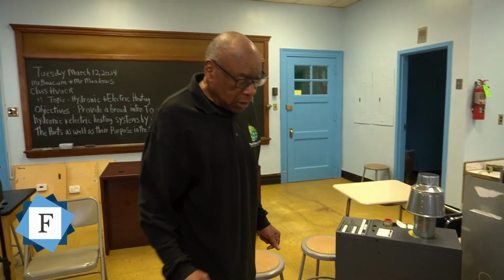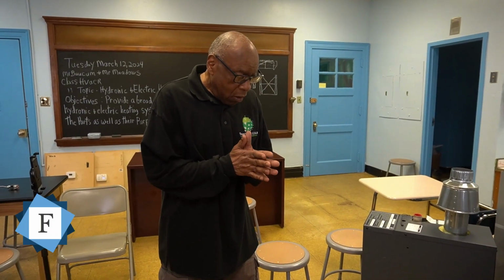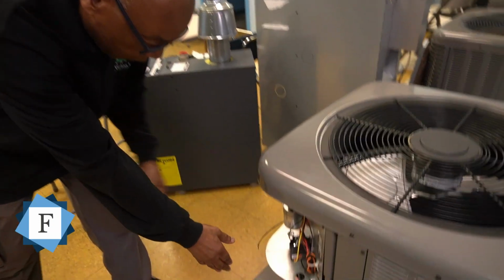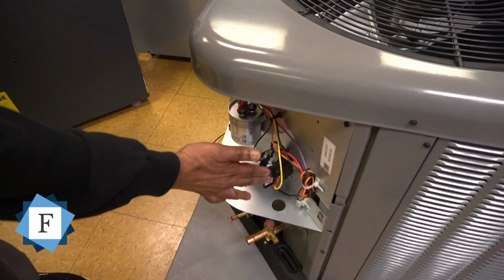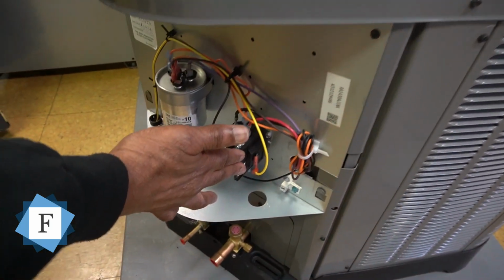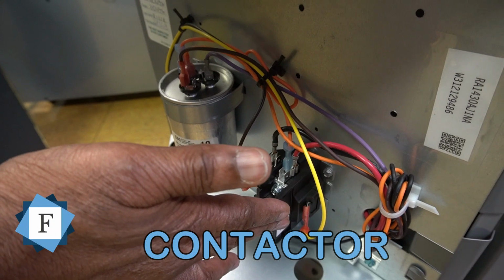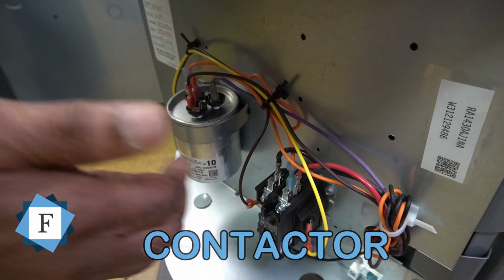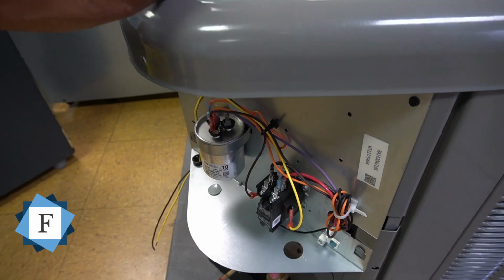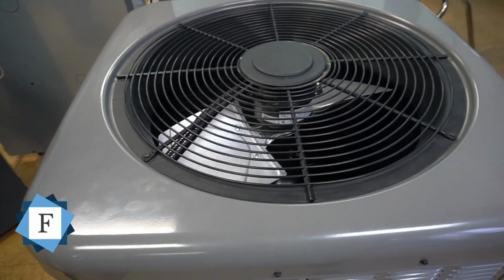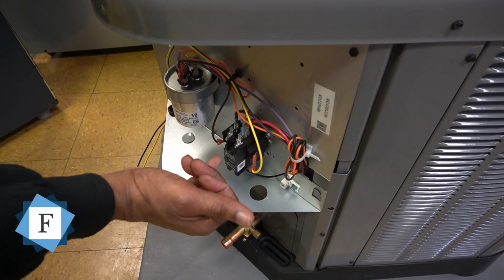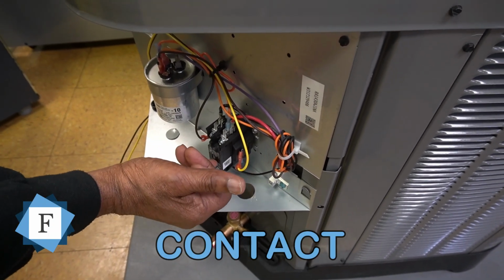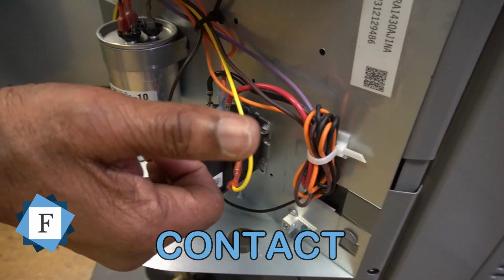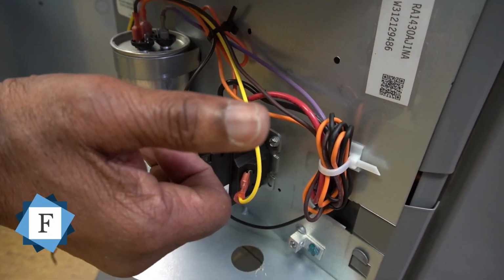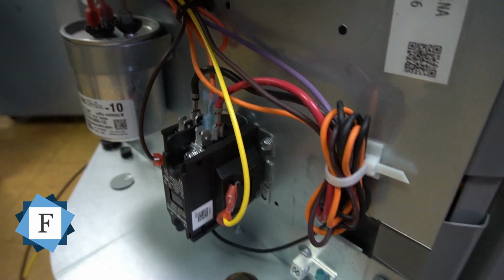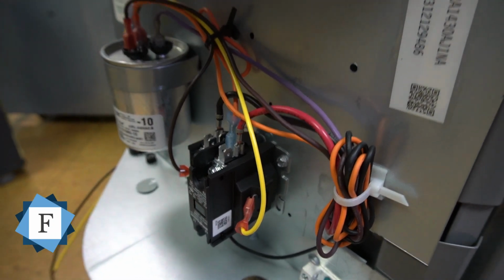Another part that makes up the condensing unit that we want to cover are these two devices here. This device is one of the main important parts that make up the condensing unit. This is the contactor. And this is the part that turns everything on, the condenser fan and the compressor, the contactor. All right. This is the actual contact, and that has to be made in order for the unit to come on.